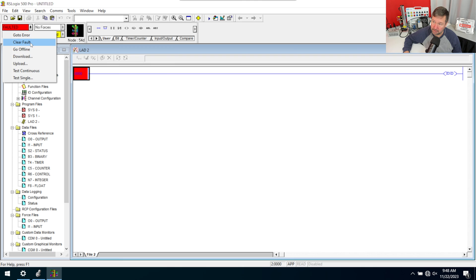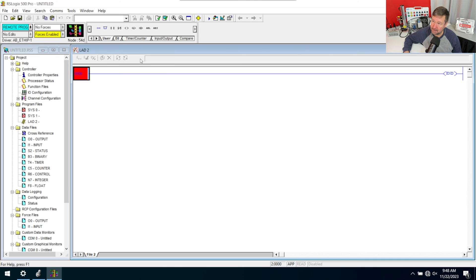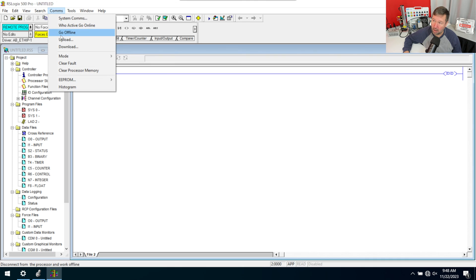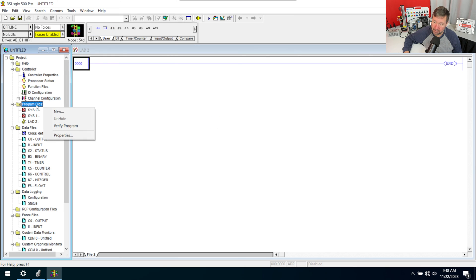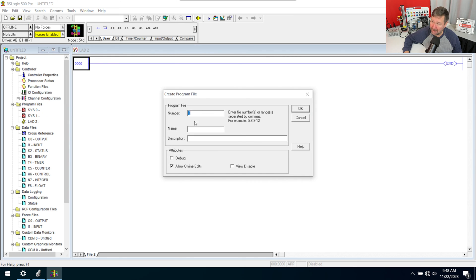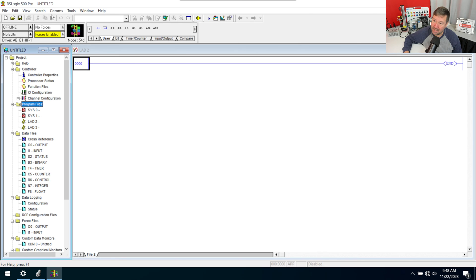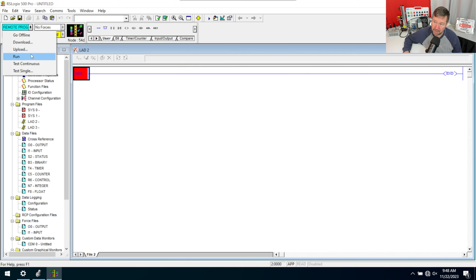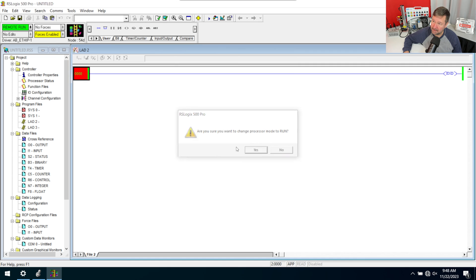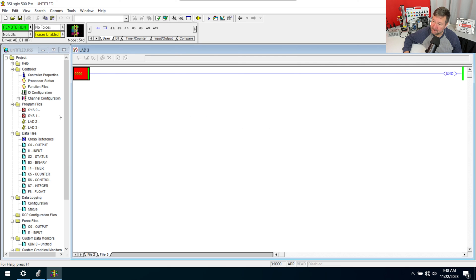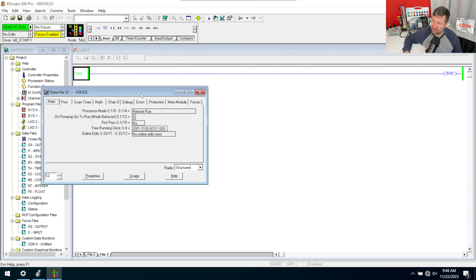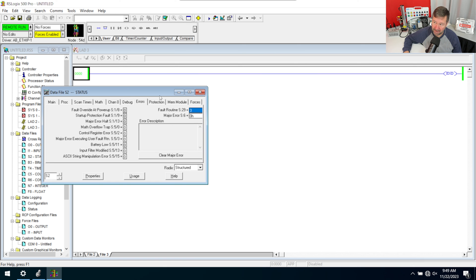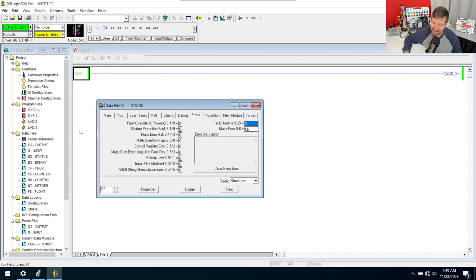So we're going to clear the fault, then go offline. Then we'll simply right-click program files, select New, and not even put a name — just click OK. Download that program. And now when I go to run mode, it will be just fine. Ladder 3 is completely empty, but because you had it specified in the fault routine here as ladder 3, it has to exist.